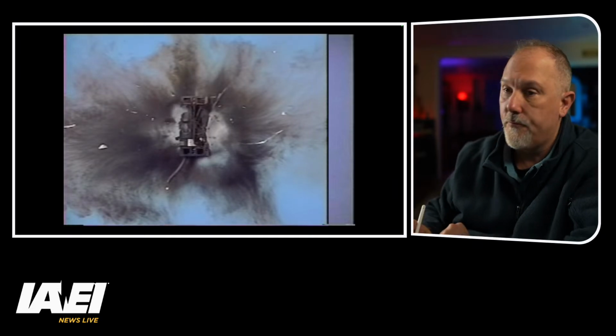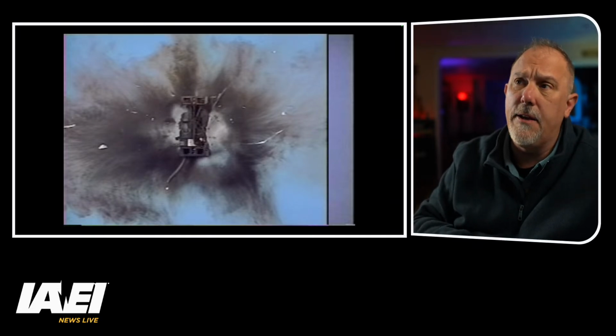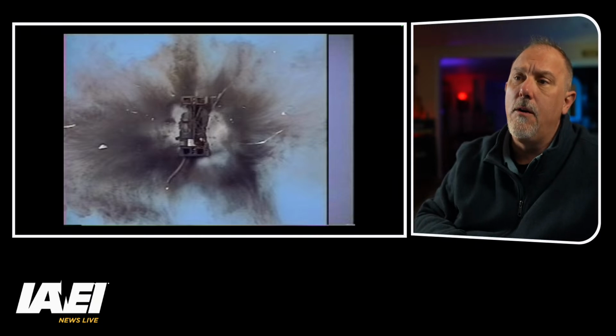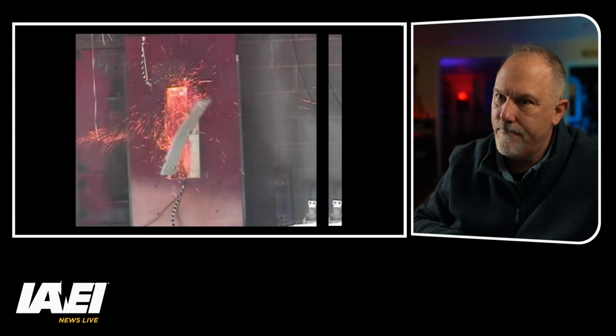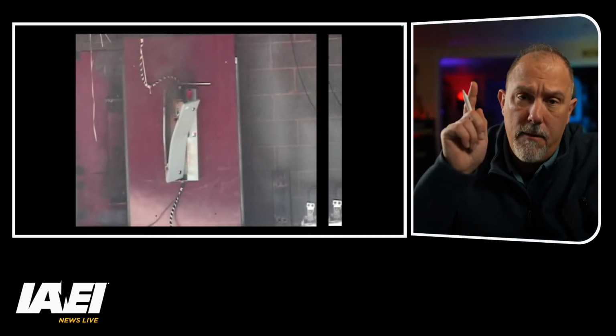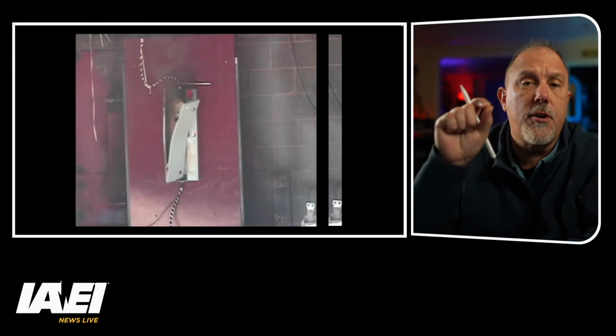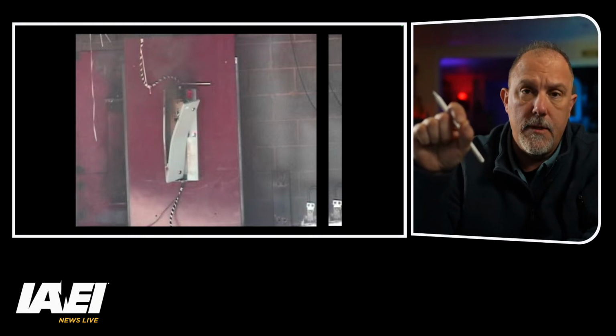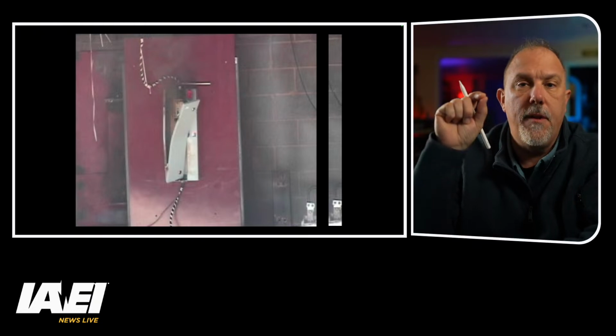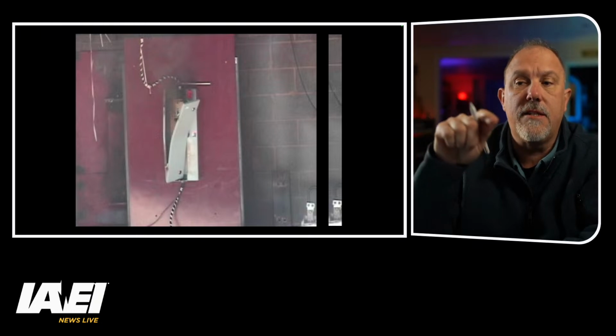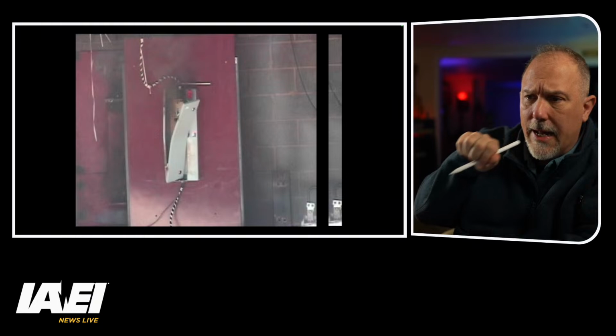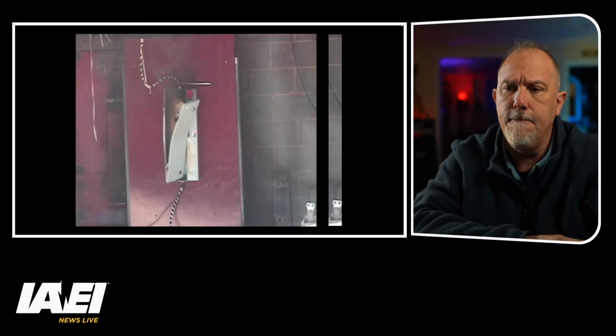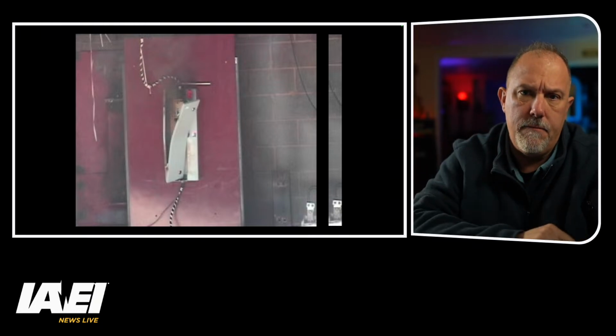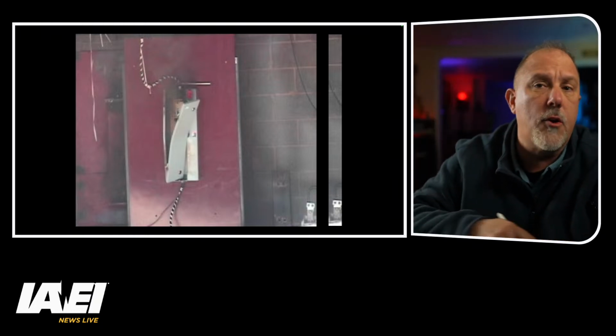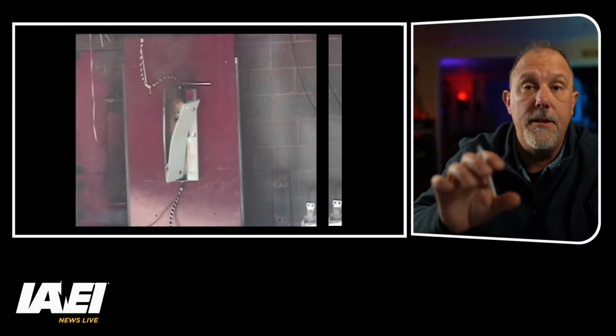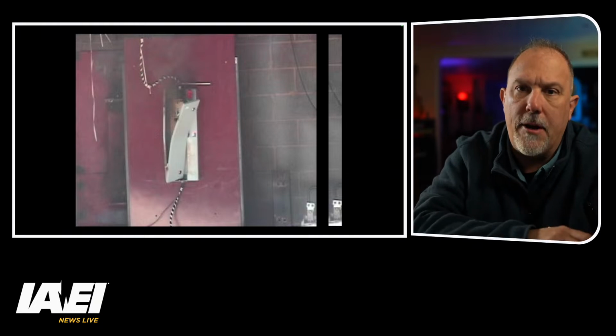Again, this is a serious misapplication. So those are two great Bussmann videos that I've seen, and I know many of you probably have seen as well, of unintended rapid disassemblies in the field. All right, so that was a demonstration of a short circuit current rating being exceeded. That's not a fault that started inside the equipment. That's a fault. If you look down there, that little black and white zebra-shaped conductor, that conductor is shorted at the end of it. So the fault current passed through the equipment, and the components inside were not able to hold it together under the pressure.